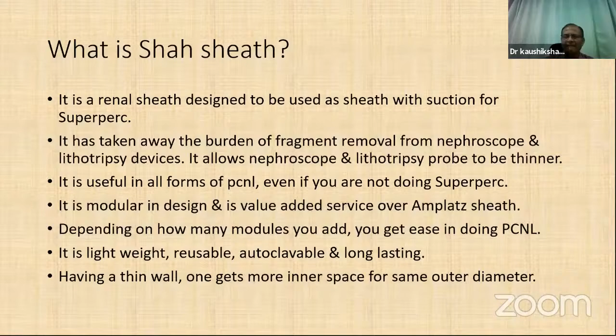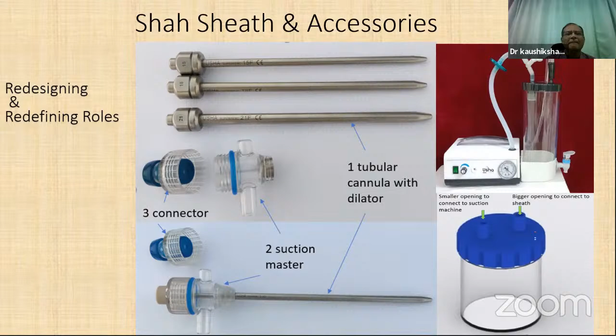This is the Shah sheath - I would redesign and redefine its role. This sheath comes with dedicated dilators. This is a suction master to add suction. This is a connector to adapt to different nephroscope sizes, giving an airtight seal. This is a low pressure suction machine with a tap on the bottle to empty it easily. And this is a stone catcher bottle to collect the stone fragments. So these are the equipment we use.